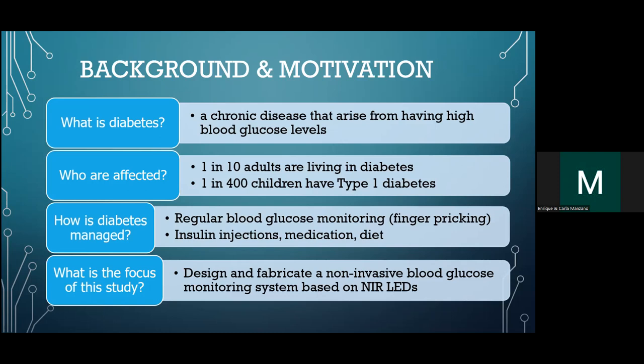This follows research published in the same journal in 2019, but uses a different spectrum. This one uses the 1550 nanometer. You might ask why another spectrum when the earlier one at 940 nanometers was already showing good results. If you observe the pulse oximeter carefully, it actually uses two LEDs — one at 660 nanometers and the second at 940 nanometers — although you only see the red one since the other is infrared. It's the same approach for the blood glucometer.